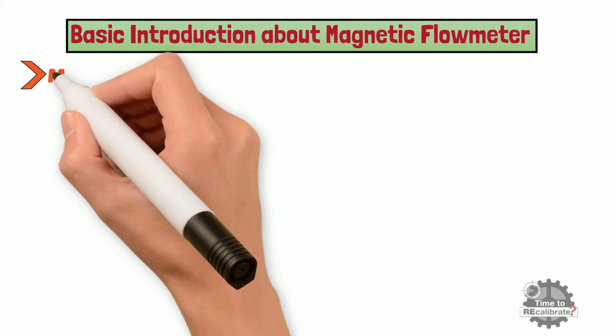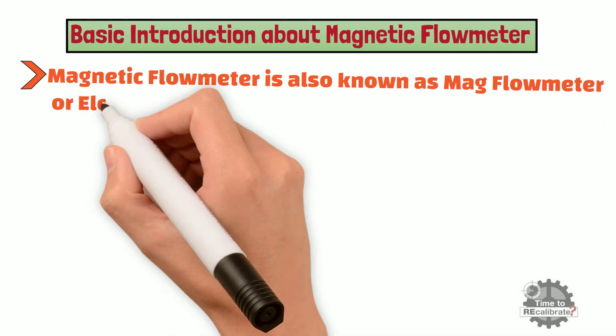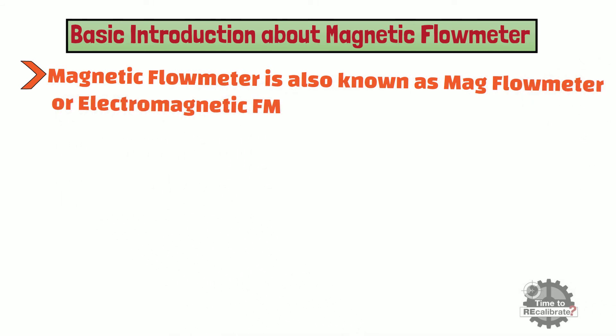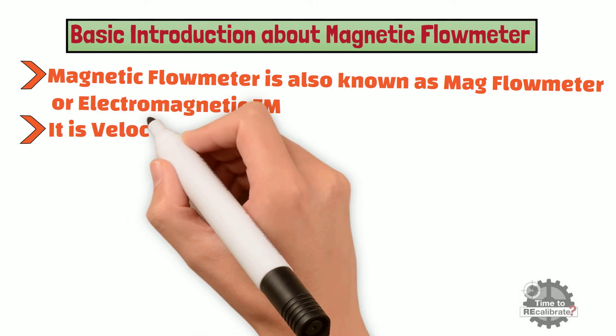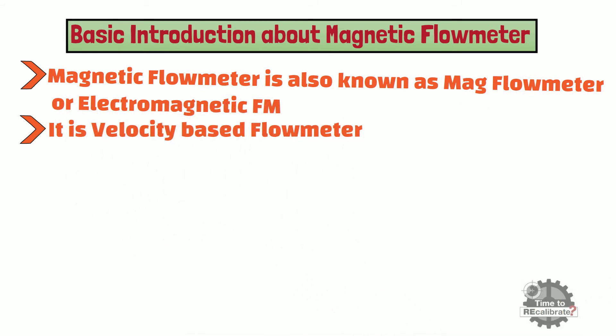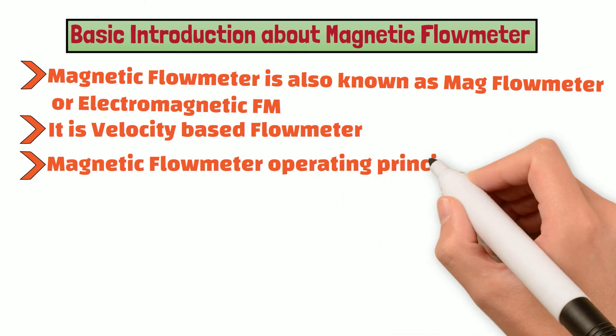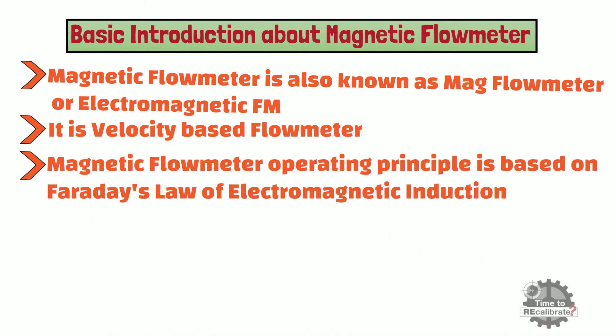Let's learn some basics about magnetic flowmeters. A magnetic flowmeter is also known as a mag flowmeter or electromagnetic flowmeter. It is a velocity-based flowmeter used to measure the volumetric flow rate of liquids. Its operating principle is based on Faraday's law of electromagnetic induction: when a conductive medium passes through a magnetic field, a voltage is generated proportional to the velocity of the medium, the density of the magnetic field, and the length of the conductor.